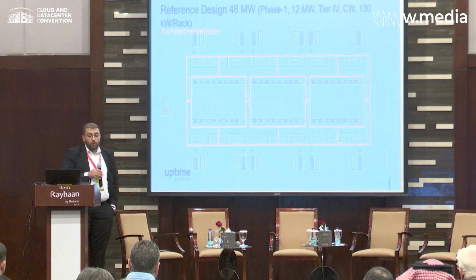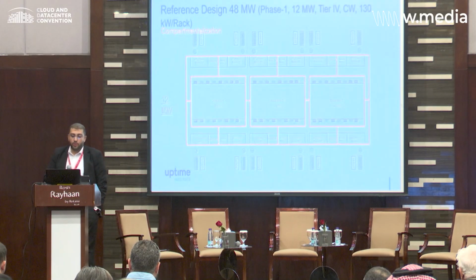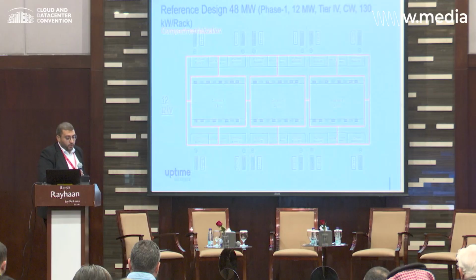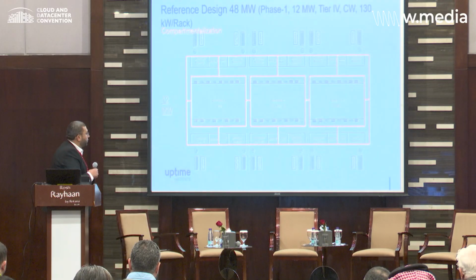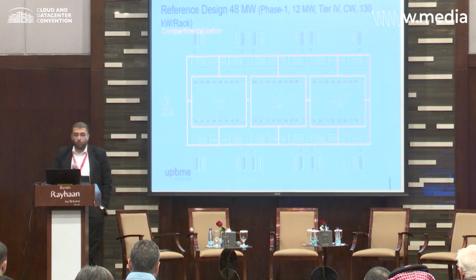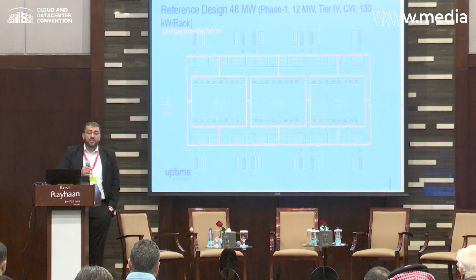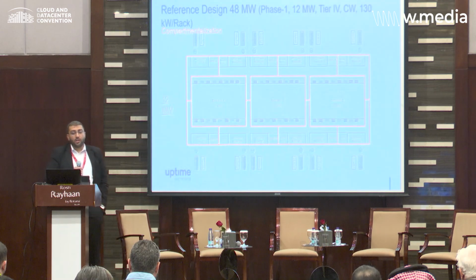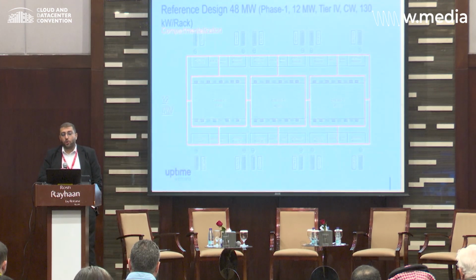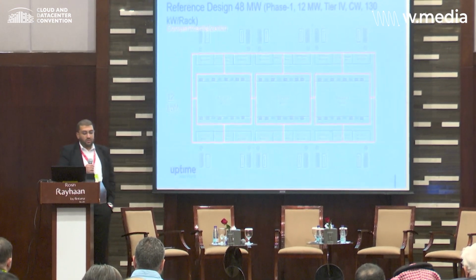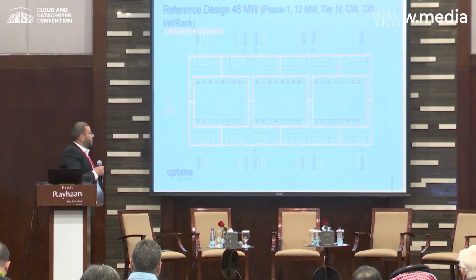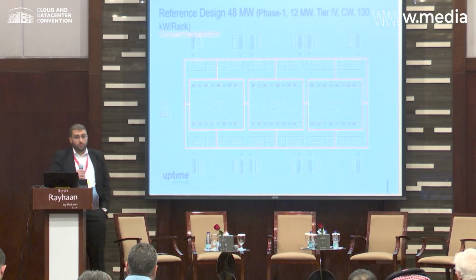Now we enter the Tier 4 world, where power and cooling must be fault tolerant. Here we are using a distributed redundant configuration, which is 4 to make 3, or 5 to make 4. This type of configuration will allow you to remove each and every cooling valve without interrupting the data center or the AI workload.